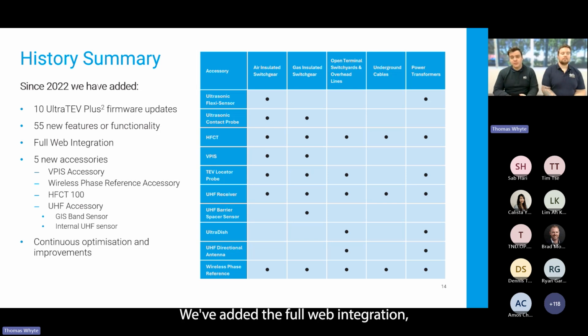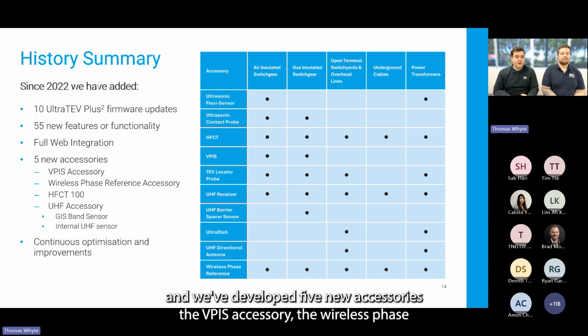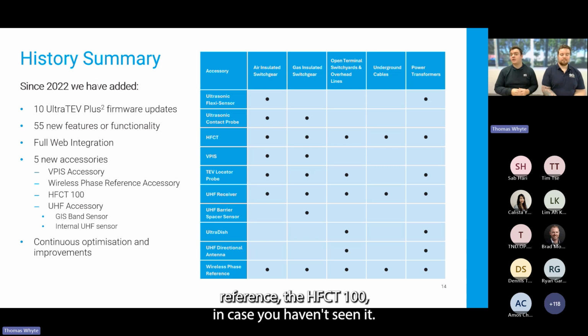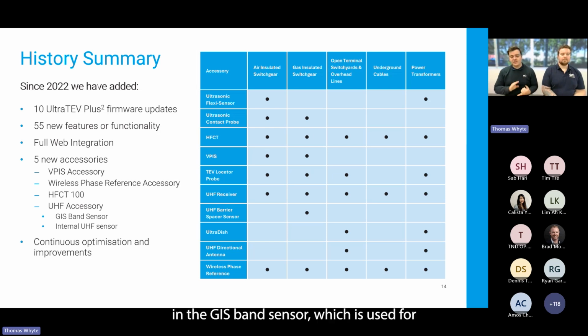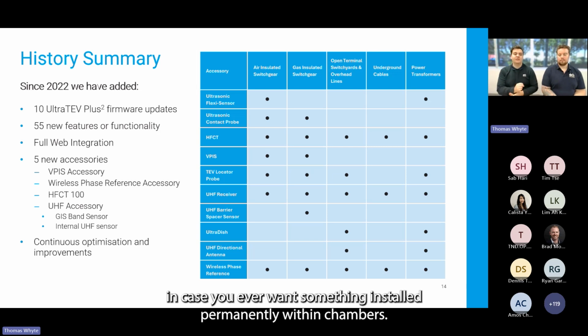We've added full web integration, and we've developed 5 new accessories: the VPIS accessory, the wireless phase reference, and the HFCT 100, in case you haven't seen it, a bigger HFCT for different cable sizes. We've also introduced 2 new UHF accessories: the GIS band sensor, used for GIS switchgear, and the internal UHF sensor, in case you ever want something installed permanently within chambers.